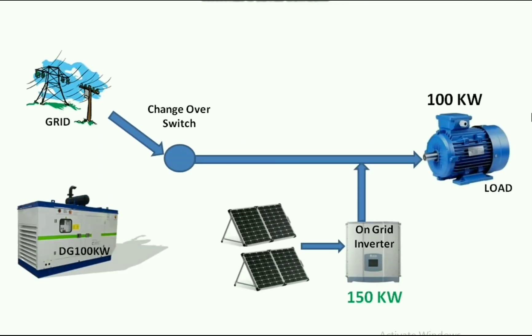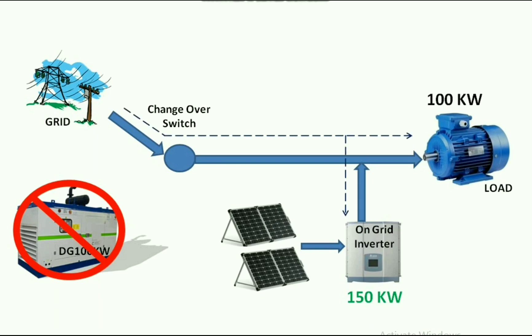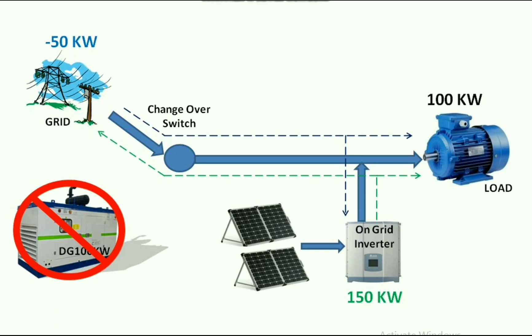For better understanding, we will increase the solar capacity to 150 kW for the above case. Similar to the previous case, when the load is getting supply from the grid, the DG will be in off condition. Initially the overall 100 kW load is supplied by the grid. But when the on-grid inverter gets supply, it starts generating 150 kW from solar. Of that, 100 kW supplies the load and the excess 50 kW is exported to the grid.